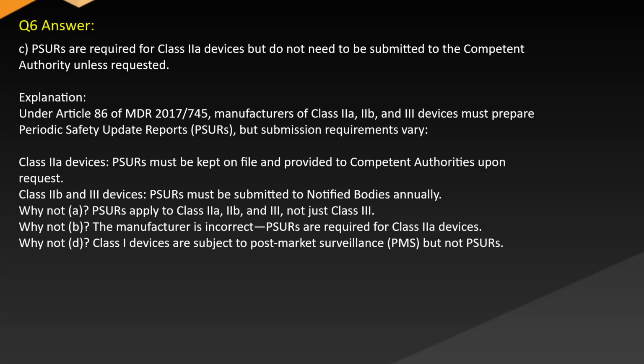Answer. C. PSURs are required for Class IIa devices but do not need to be submitted to the competent authority unless requested. Explanation. Under Article 86 of MDR 2017/745, manufacturers of Class IIa, IIb, and III devices must prepare periodic safety update reports, PSURs, but submission requirements vary. For Class IIa devices, PSURs must be kept on file and provided to competent authorities upon request. For Class IIb and III devices, PSURs must be submitted to notified bodies annually.